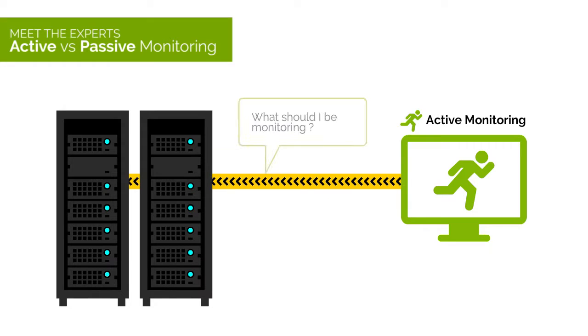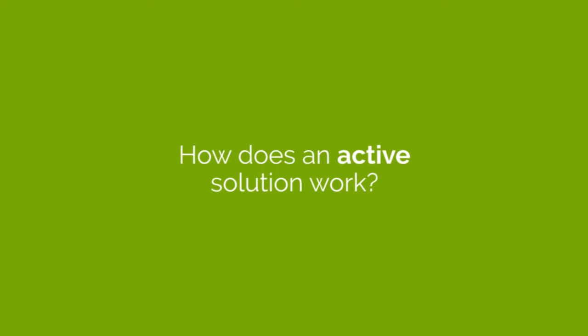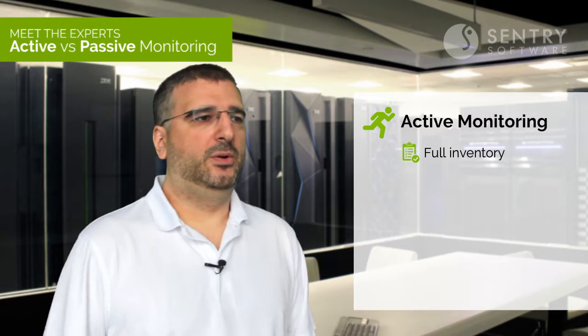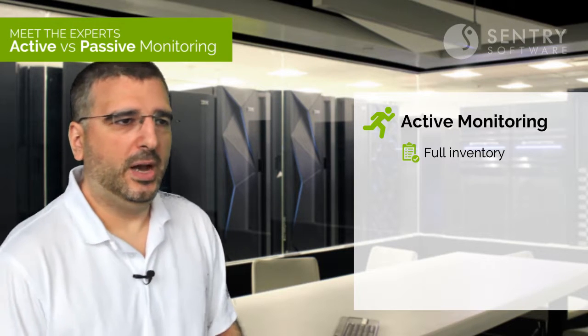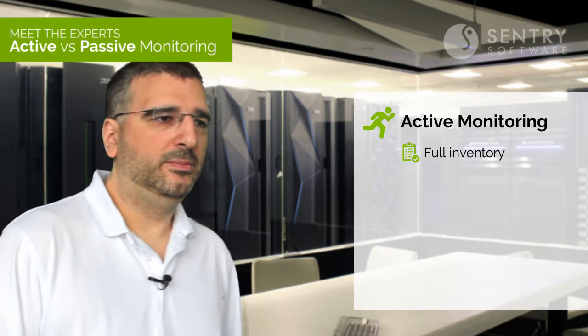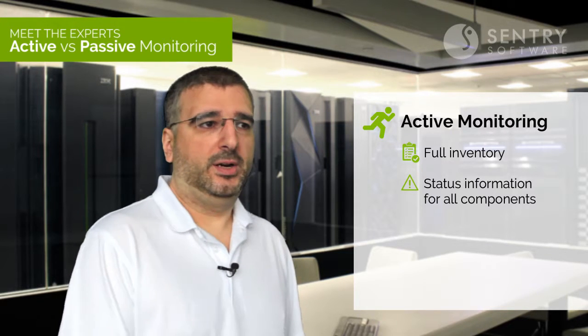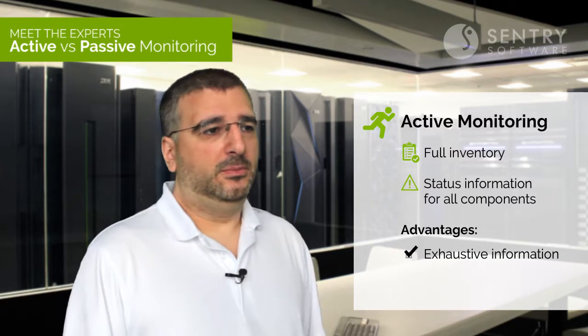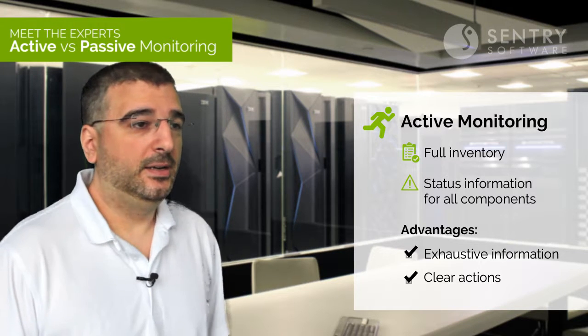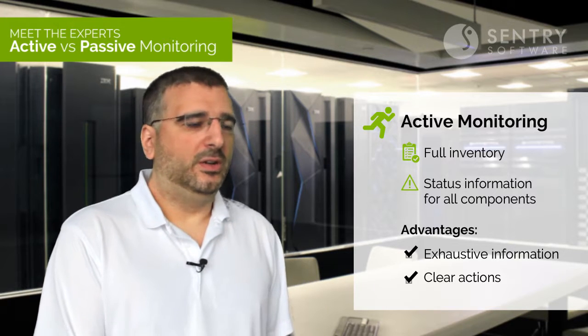What's your status? What should I be monitoring? What have you got in your system? An active solution would take an inventory, make a list of all the components and all the part numbers, and then start asking. You told me you had three CPUs — what's the status of all of them? If something goes down, you know not only what it is, where it is, and what its part number is — the actions are clear. It's not some cryptic message. It's saying that I've gone out, asked the monitored element what's wrong, and it's told me.